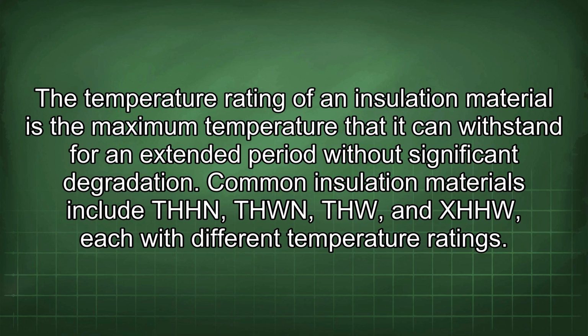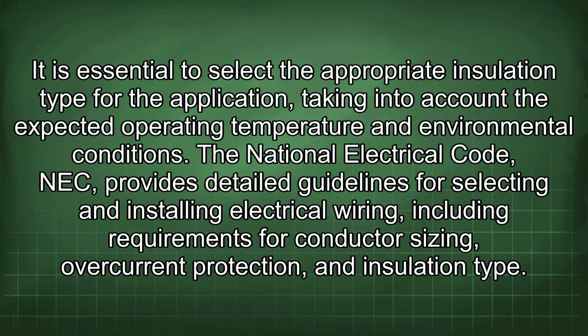Common insulation materials include THHN, THWN, THW, and XHHW, each with different temperature ratings. It is essential to select the appropriate insulation type for the application, taking into account the expected operating temperature and environmental conditions. The National Electrical Code, NEC, provides detailed guidelines for selecting and installing electrical wiring, including requirements for conductor sizing, overcurrent protection, and insulation type.